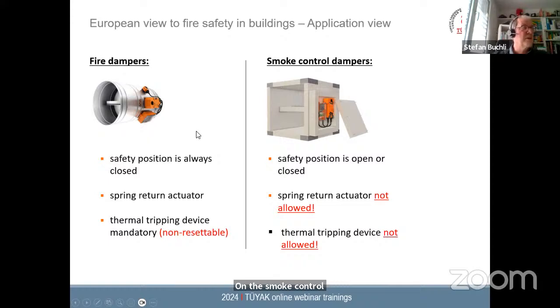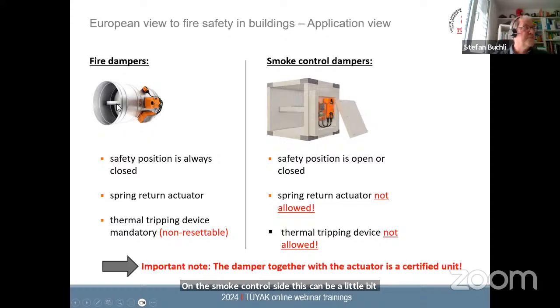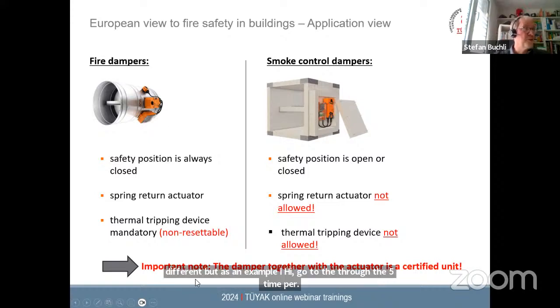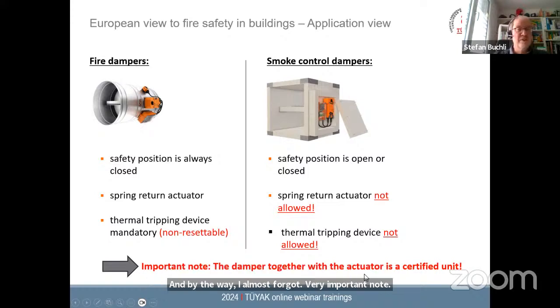But as an example, I go to the fire damper. And by the way, I almost forgot a very important note. The damper together with the actuator is always a certified component or unit. So the fire damper manufacturer mounts our actuator, as an example, on his dampers. And together, as a unit, the actuator and the damper go through the certification process. That means life cycle testing, and that means fire testing.